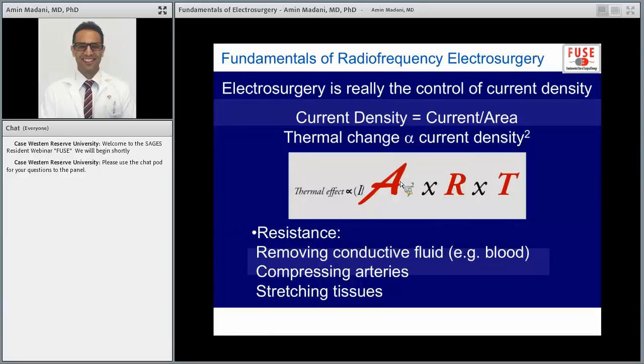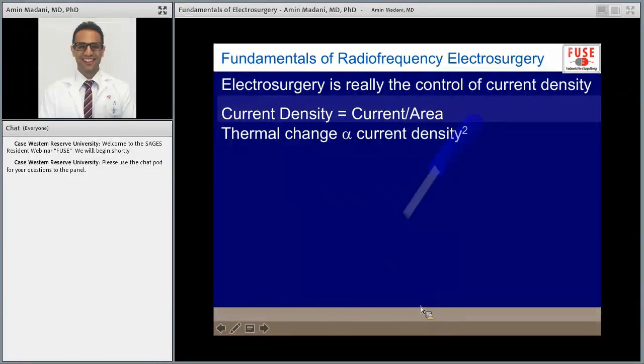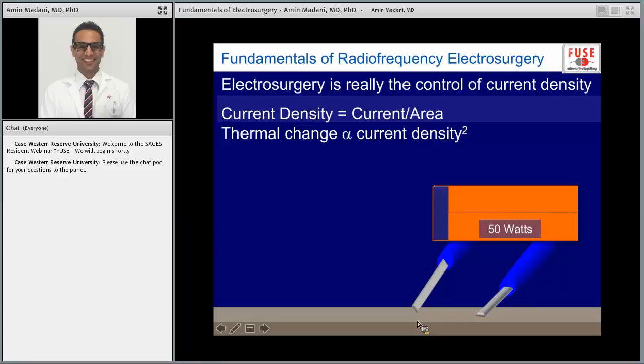Now this other thing is called current density, and I'm just going to talk about this a little bit. Current density is the amount of current that goes through your circuit divided by the surface area with which you make contact with the tissues. So imagine you have your monopolar device. You can either buzz using the very tip, or you can use the flat part. The tip is going to be very low surface area, and because it's low surface area, the density is going to be very high.